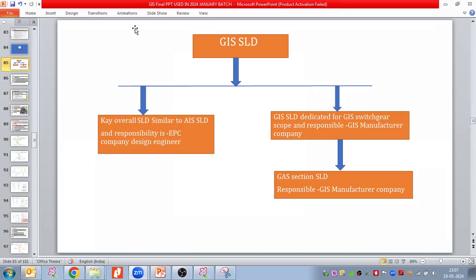Okay. For example, if I use the 132 kV GIS, in that case, will the surge arrestor be outside or inside the GIS? See, generally outside, fully. Unless you don't have the space. Suppose you don't have the space, you cannot put it outside, and in that case, you take it inside. But if you are taking it inside, then the enclosure insulation coordination and your GIS enclosure insulation cost will increase. And once the insulation cost increases, then your GIS cost will also increase. So try to put the surge arrestor outside of the GIS.